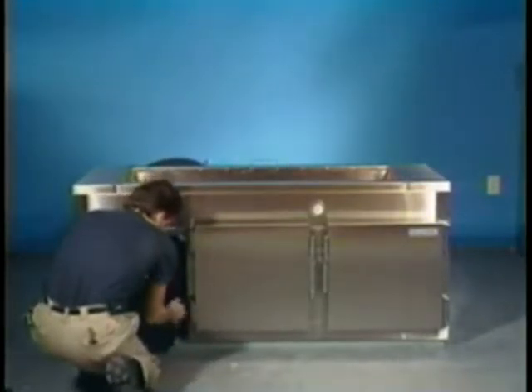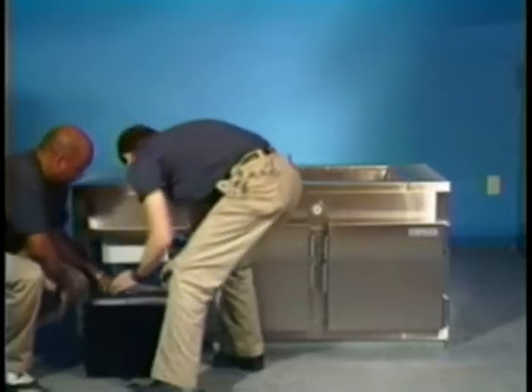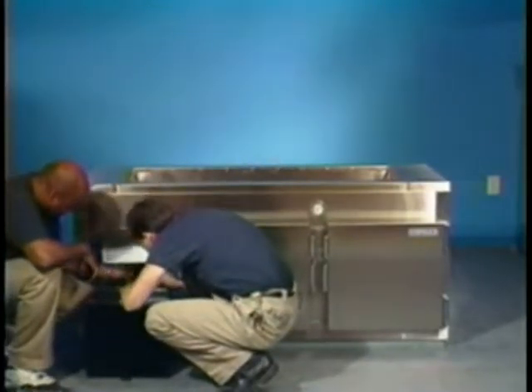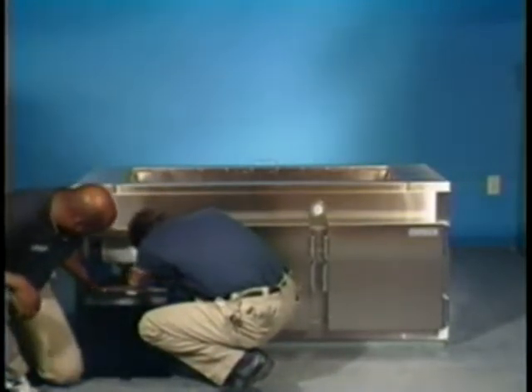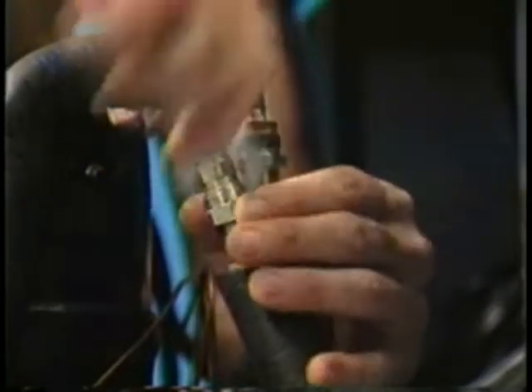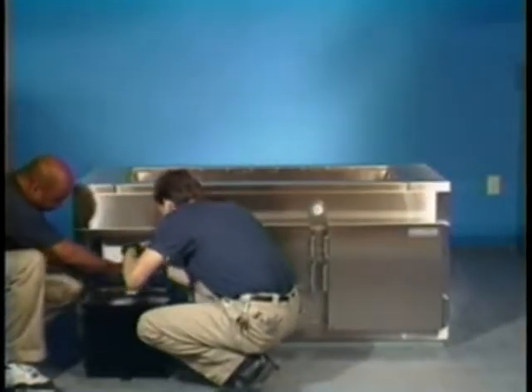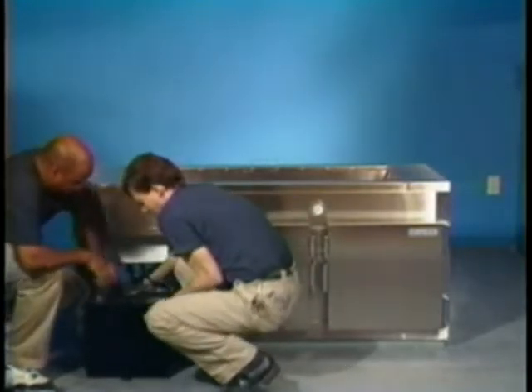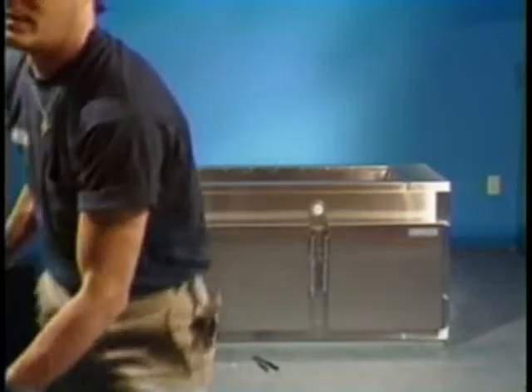Slide the condensing unit out of the unit and place it on the deck in front of the unit. Using the same procedure as was used to locate and disconnect the refrigeration lines in the back of the evaporator, disconnect the lines in the back of the condenser. With the two ¾ inch open-end wrenches, you can now remove the refrigeration lines from the unit. Remember, hold the male fitting steady and turn the female fitting counter-clockwise. Next, locate the power cord running from the condensing unit to the stainless steel junction box and disconnect it. Then move the condensing unit to a safe place.